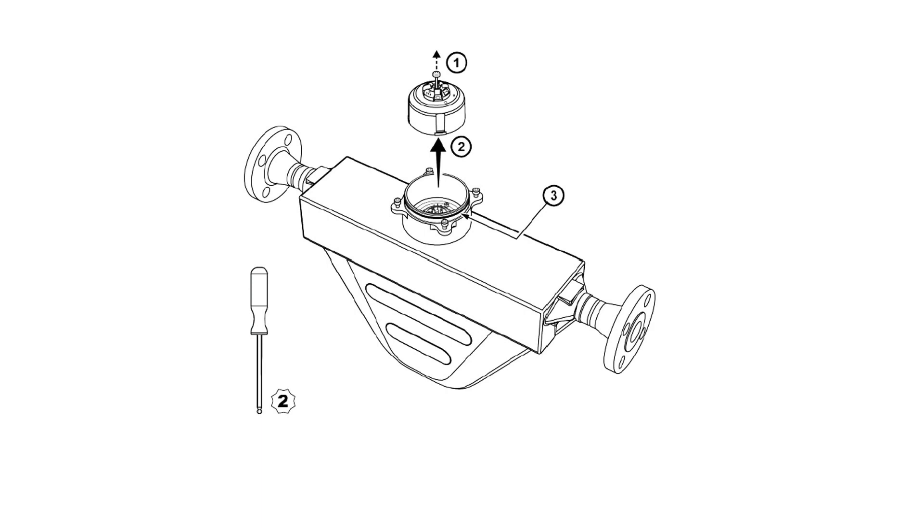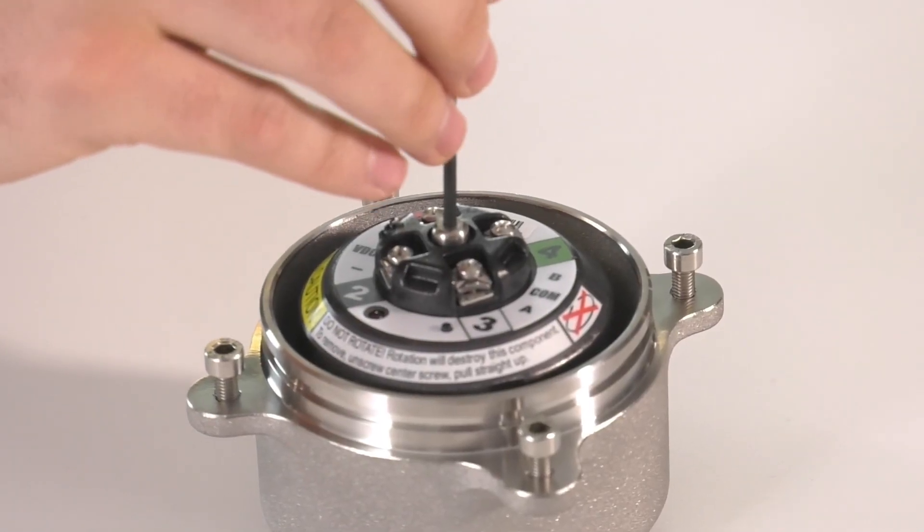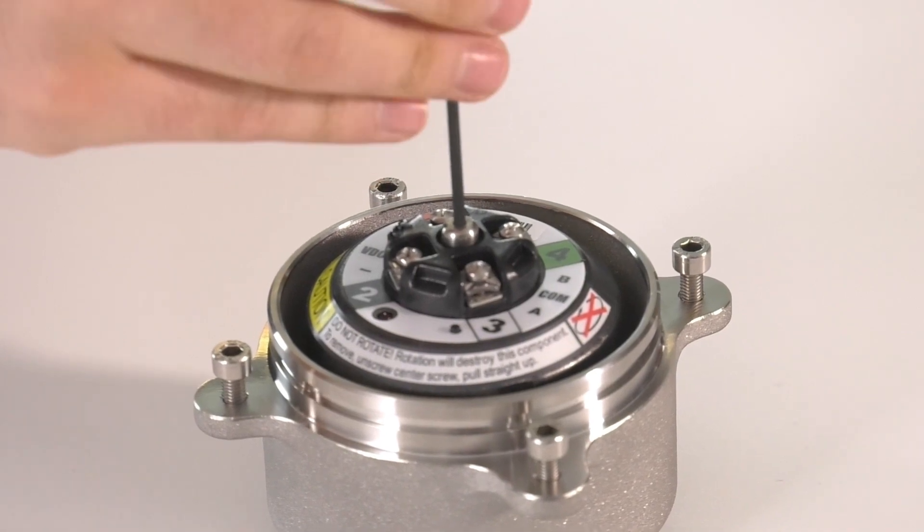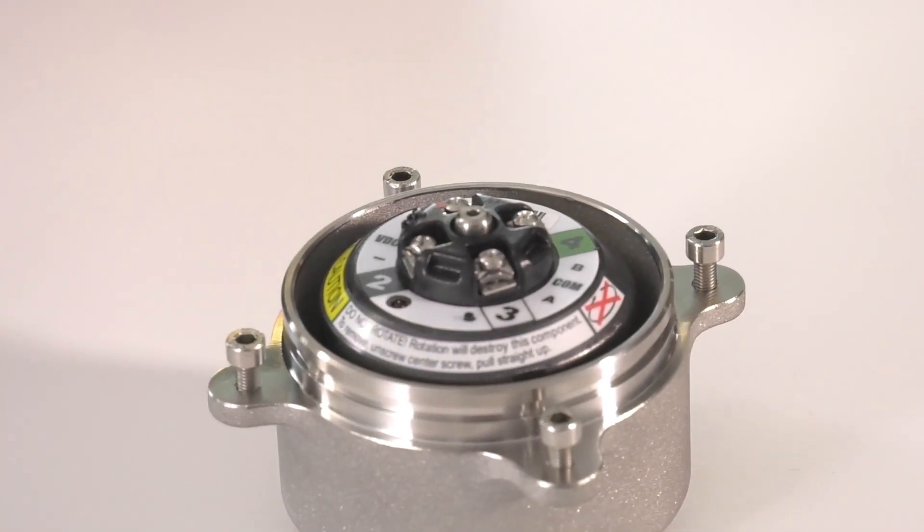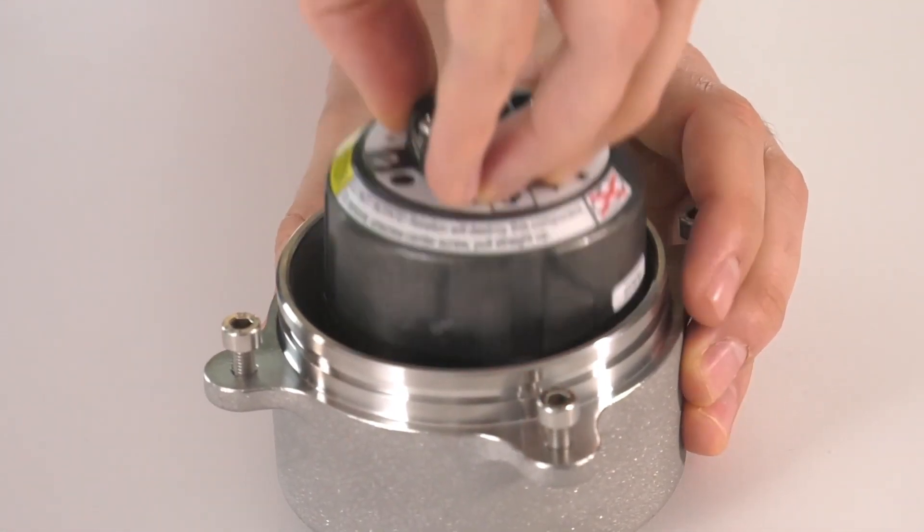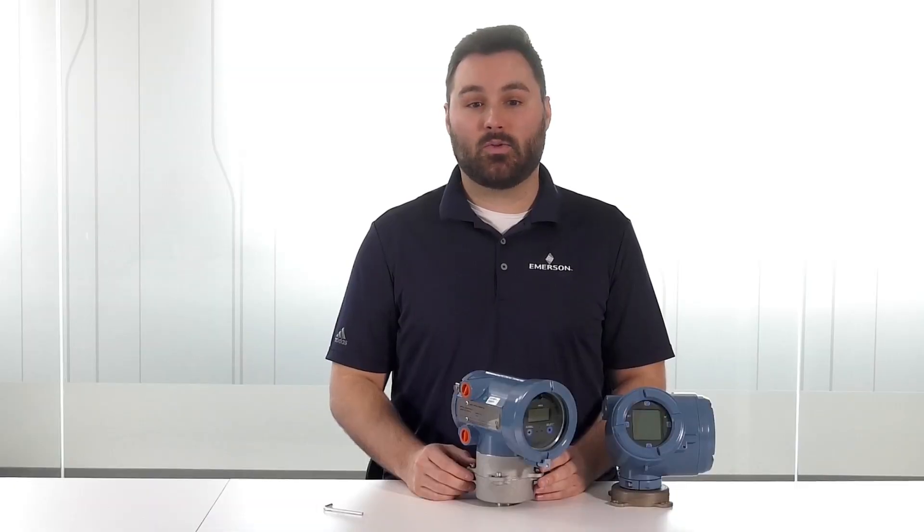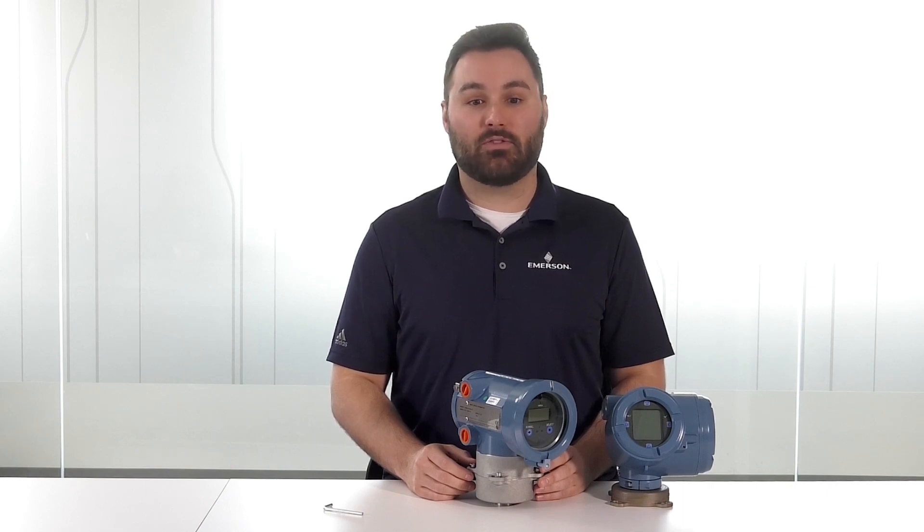Next, we will remove the 700 standard core processor. First, loosen the center core processor with a 2.5 millimeter hex driver. After, lift the core processor up. Please note not to twist the 700 core processor when removing it from the sensor mount because it can damage the feed through pins.